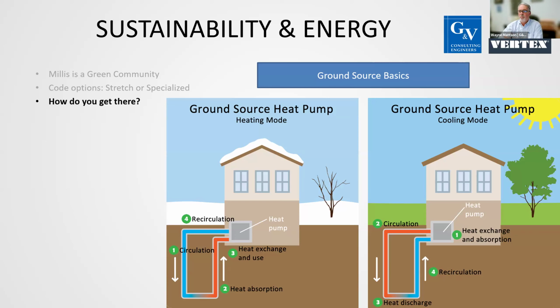So the geothermal system, I'm glad you brought that up. The geothermal system that we've been using is called a standing column closed loop. I don't have a picture of it in the slide, unfortunately. I didn't really go too far into this, but it's a pipe within a pipe. So we actually don't use any water from the ground, nor do we put any water into the ground. It's like a long vertical heat exchanger where water from the building goes down the center pipe, and then the water flows back up the outside of the pipe and extracts heat or rejects heat into the ground surrounding it. So there's no cross-contamination of the heating system water and the groundwater, nor do we have to replenish any systems. So it's kind of like an evolution of what you're discussing. But yeah, smaller systems, residential systems, small commercial systems, is exactly what you just discussed and exactly what you see. Larger schools, we've gone a different route.